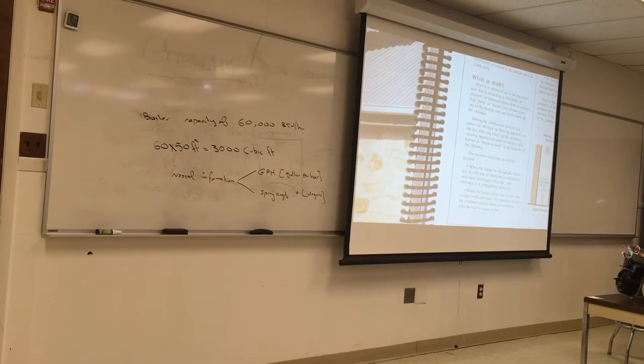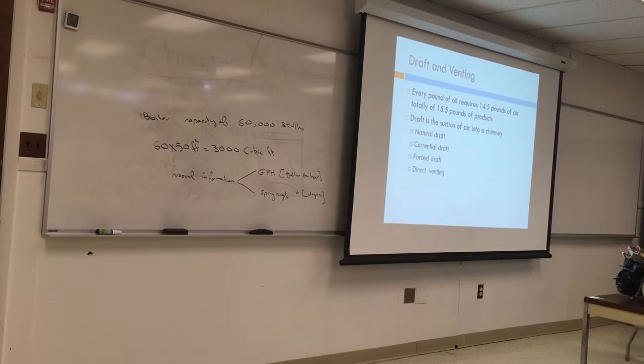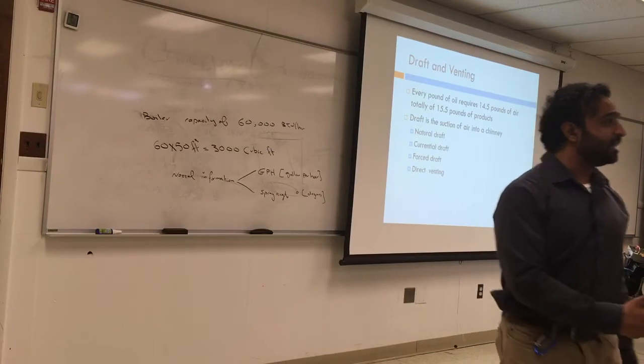Draft and venting. So for every pound of oil, a gallon has how many pounds? 7.4. We talked about that in week 1. For every pound of oil, we need 14.5 pounds of air, which totally will give us 15.5 pounds of product. Usually when we think of gas, we don't think of weight, but this is how much weight we're producing.